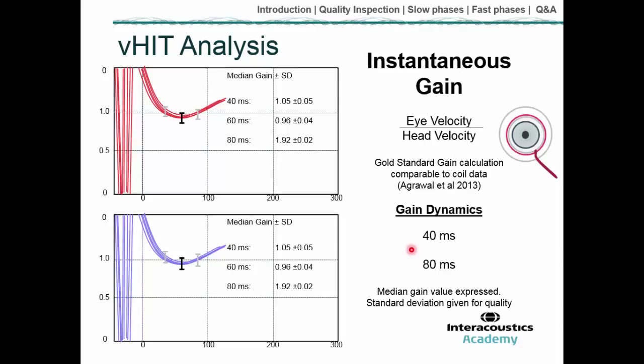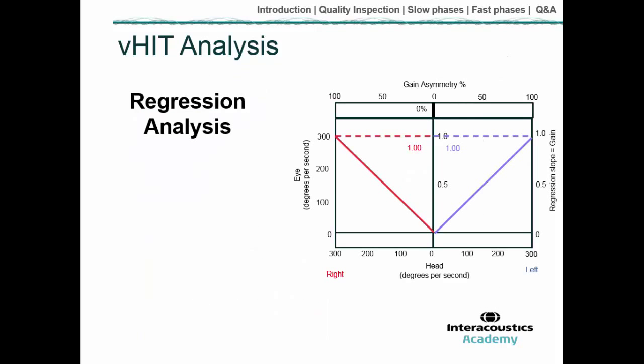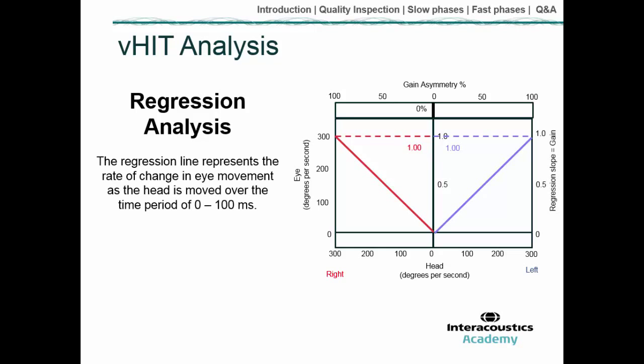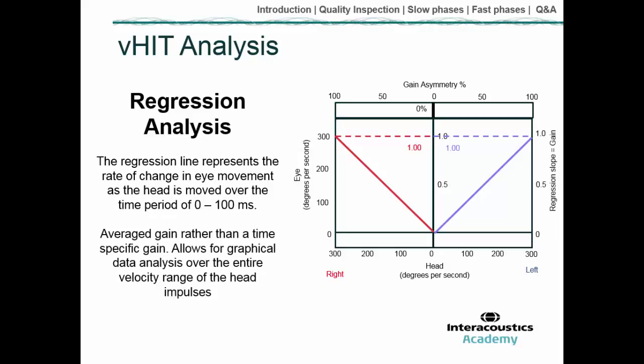For beginners, I suggest focusing on gain at 60 milliseconds as this is most useful. The instantaneous gain at 60ms is a median gain with associated standard deviations, which are important for assessing recording quality. In addition to instantaneous gain, a second graph shows regression analysis, which describes the rate of change in eye movement as the head is moved over the 0 to 100 millisecond time period — essentially an average gain over a wide time window.